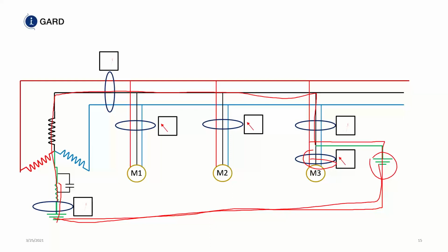And I've had this challenge with Southern Ontario and many other jurisdictions throughout North America: if I can't find a fault in less than 1 hour, I will buy lunch for everyone in the facility. I have never had to buy lunch for anyone in the facility because we can always find the fault in a short order of time. And we don't have to open up any doors to go around the three-phase conductors because our equipment is so sensitive, we can actually pick up current around conduit or around bus duct. So we don't have to open up. We have an arc flash mitigation technique. We didn't shut anything down, because while this fault is on the system, nothing has been shut down.